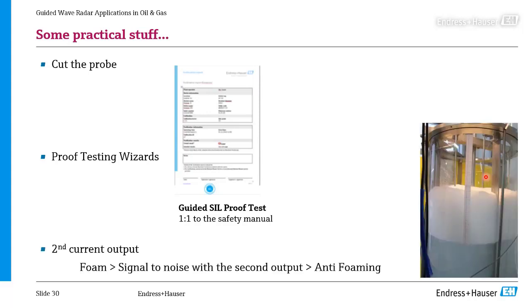Last but not least, in those devices we have a second current output, which you can use creatively. For example, to see foam building up, we can set a threshold with the second current output, and whenever you reach it, automatically dose in anti-foam agent. We had one case in Switzerland, a chemical wastewater tank, where this saved around 80% of the anti-foam agent costs for the customer, because you only dose it when it's really needed. That's the offering a guided wave radar can give you.